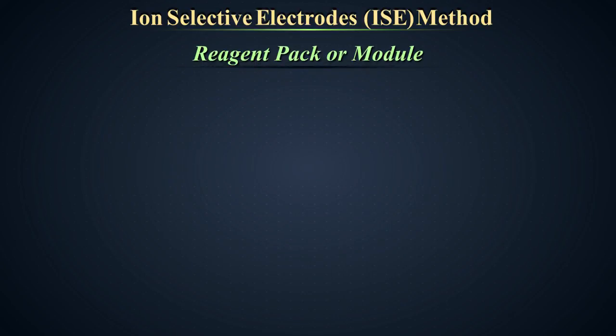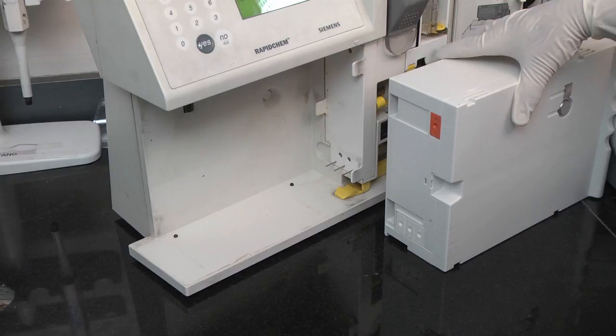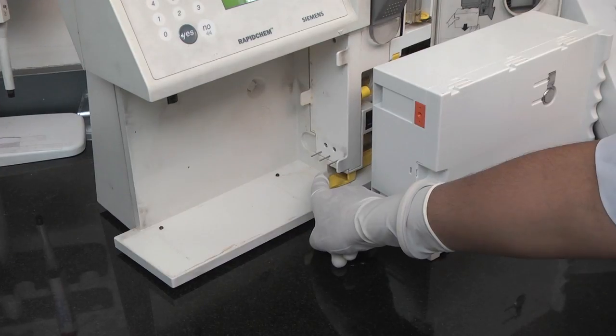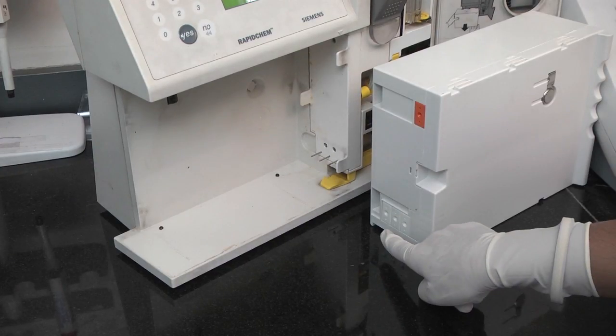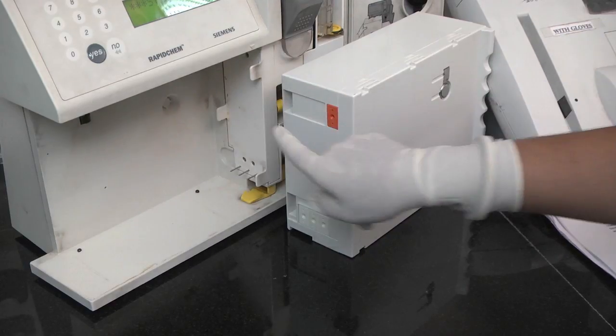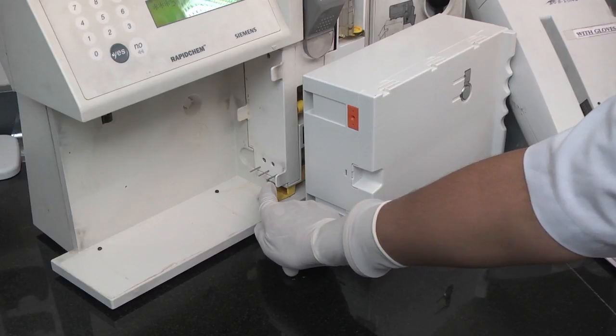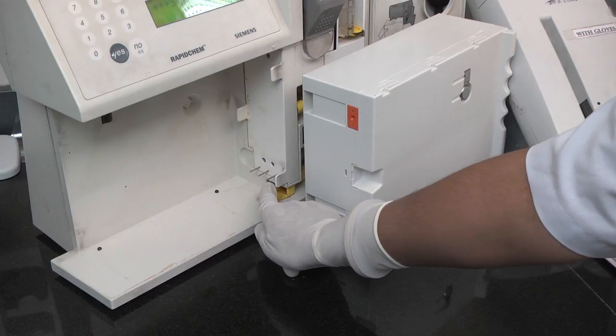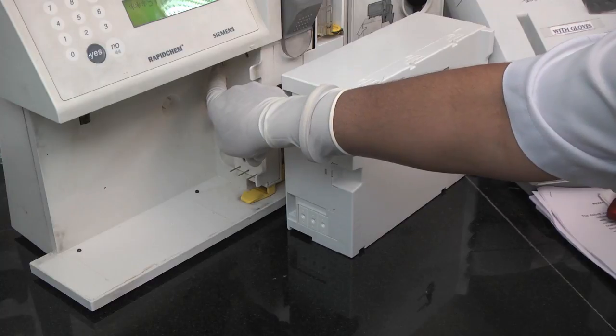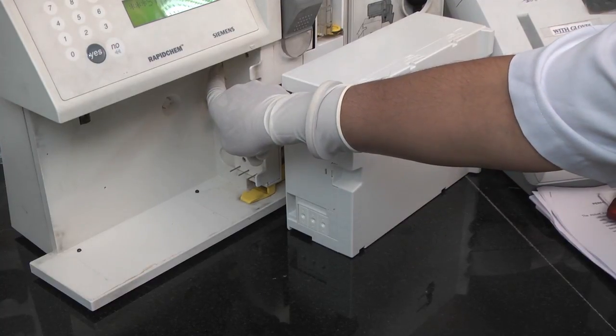Reagent pack or module. The reagent pack is a rectangular box which stores the reagents in the lower half and the waste is generated in the upper half. The left side of the pack has three inlets for the reagent tubes on the main body of the analyzer and also one inlet for the waste generated.